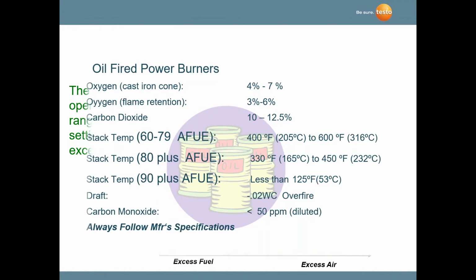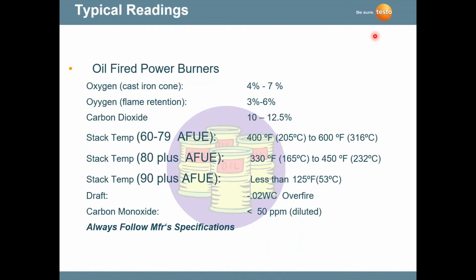Couple recommendations here. And these are typical readings. Again, these are not Testo readings. These were put together by a number of manufacturers, OEMs that we contacted. And these are some typical readings on oil-fired power burners. And again, I like to stress that these are typical readings, ballpark readings. You need to follow the manufacturer specifications. They're the experts on their equipment.